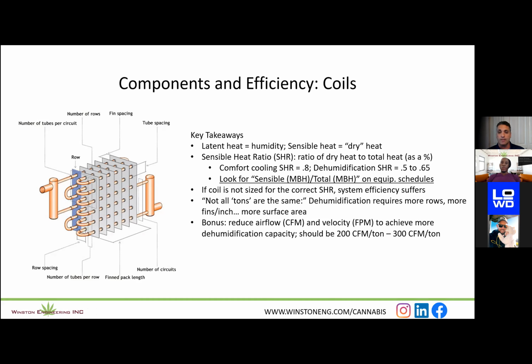So one thing that we always say is that not all tons are the same. Probably the best way to describe this is if you have a 10-ton unit that is designed to serve a comfort cooling application, you may have a 2 or 4-row coil. If you have a 10-ton unit designed to serve a flower room, you're probably going to have a 6 or an 8-row coil, something in that ballpark, right? So just hearing tonnage and knowing that you have the quote unquote total tonnage covered does not mean that you have an appropriately designed system for the application.